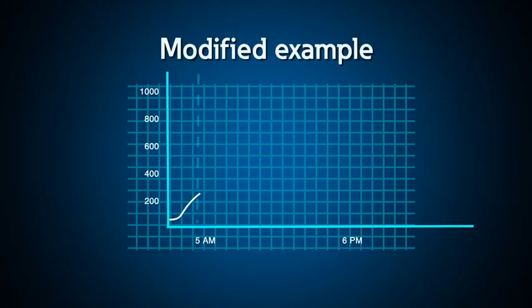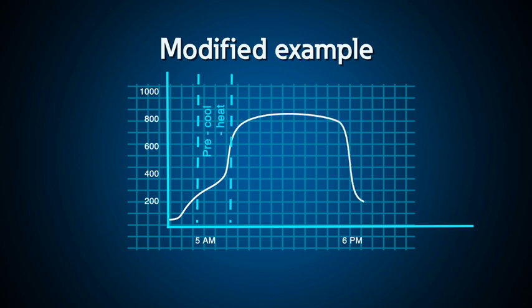By closely watching this on the power expert meter, we were able to fine-tune the HVAC system to pre-cool and preheat the building starting at 4 or 5 a.m., saving the customer a lot of money every month. The demand comparison is also a great way to illustrate demand reduction techniques for utility incentive programs.